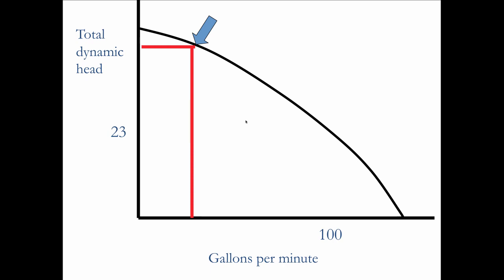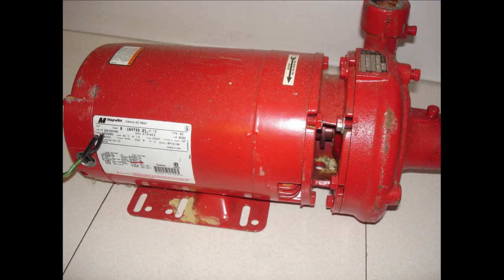All of this is cured in modern times by smart pumps that have ECM motors on them, because the pump will just automatically find itself anywhere in this slice of pie. It'll just drift around until it finds exactly what you need, and it'll do that without building pressure. So that's modern times. But this is a single speed circulator.